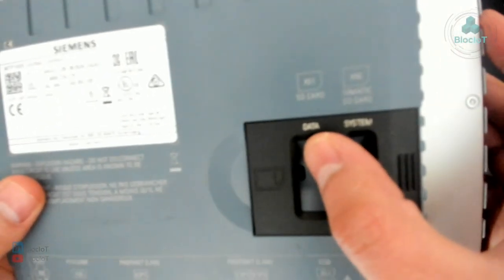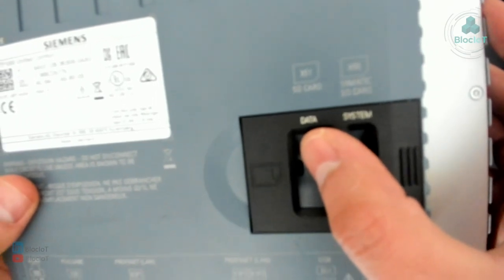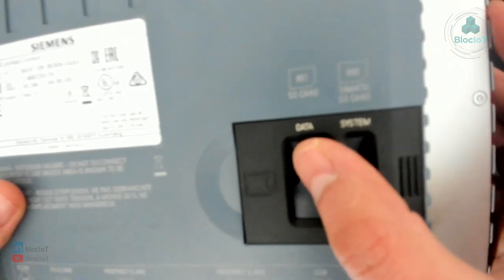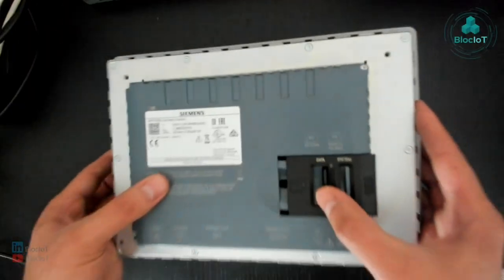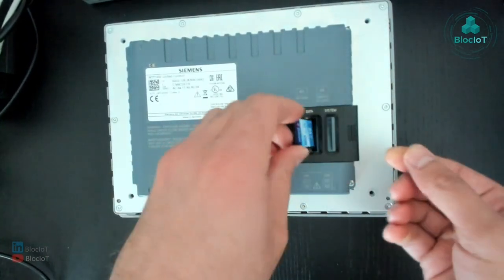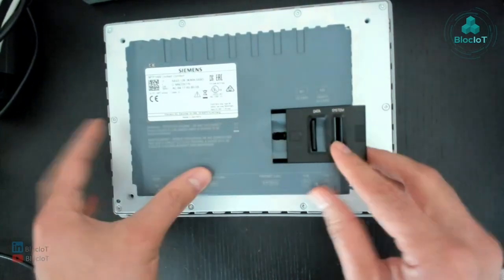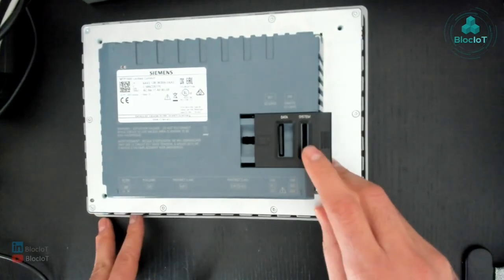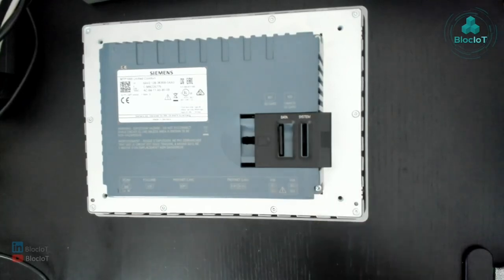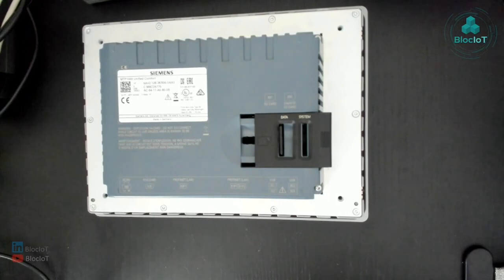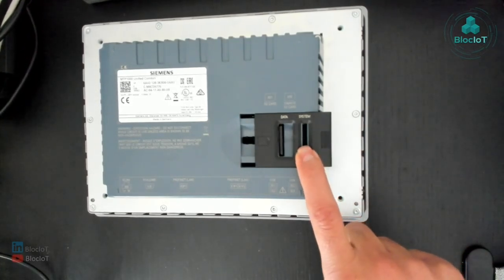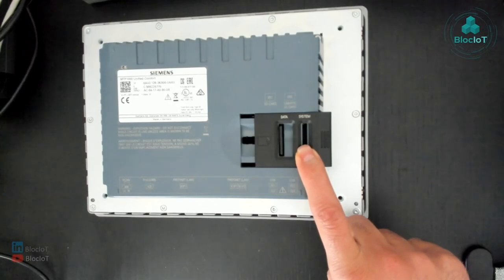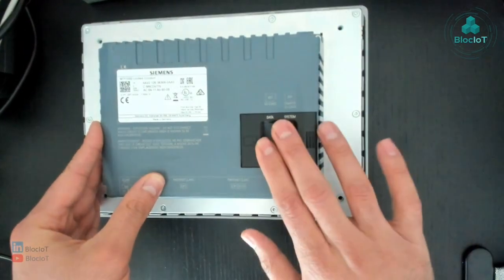And this SD card can be literally any type of SD card. As you see here, I'm just using a regular 64 gigabyte of SD card. And okay, so for the next one, the system slot, you have to use a Siemens SD card. Why? Because this slot is used for, you know, backing up the program of the HMI or backing up the entire thing or makes an image of the panel for disaster recovery purposes. In other words, if something goes wrong with your panel and you have this SD card in this slot, you just simply detach it and put it in a new panel and it's just working the same as the older panel. So that's about the SD cards.